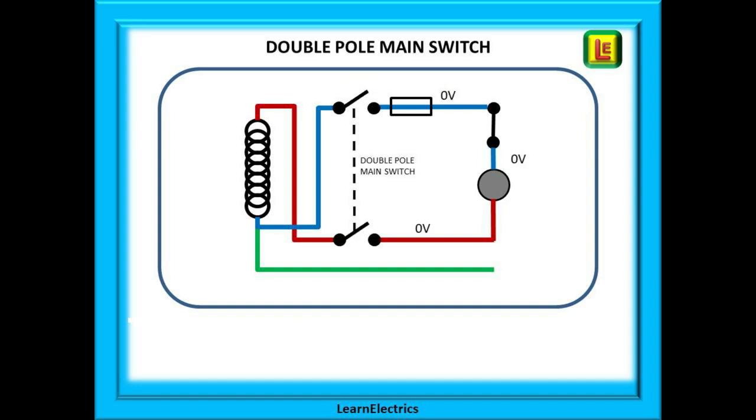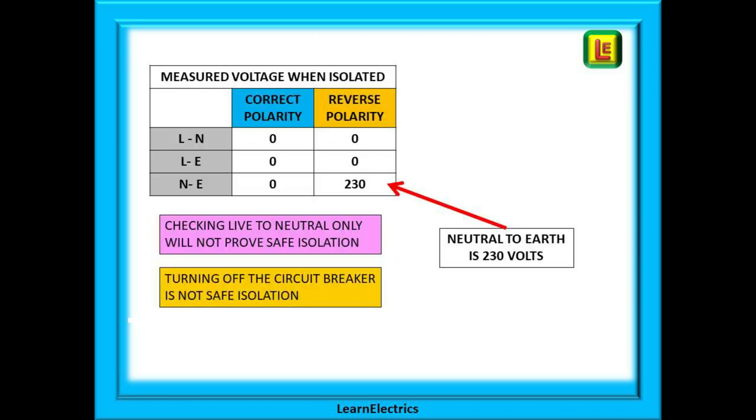But look, if we make the main switch a double pole device, both contacts open. Even if the property has reverse polarity, when the main switch is opened all voltage in the house is zero volts. However, most times we will be isolating just at the circuit breaker, a single pole device. When carrying out a safe isolation, it is therefore very important that we check all combinations of connections.